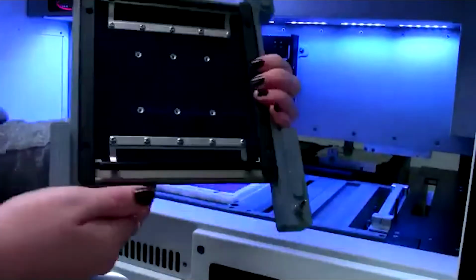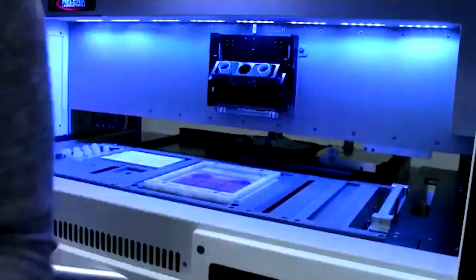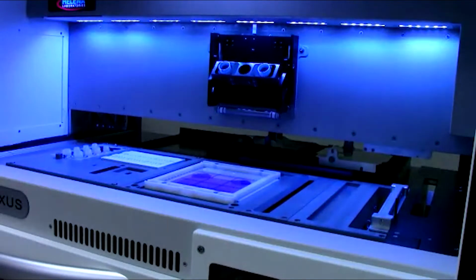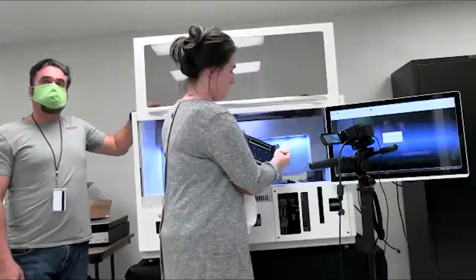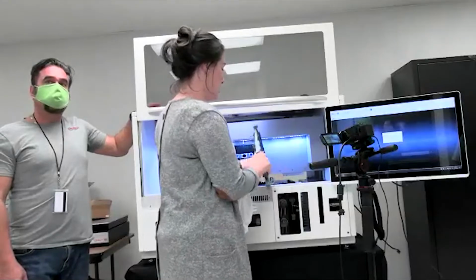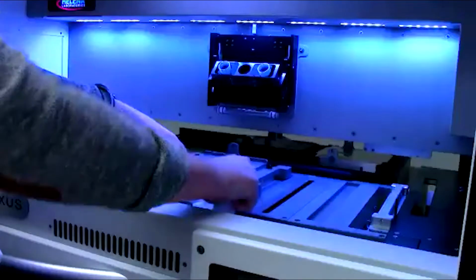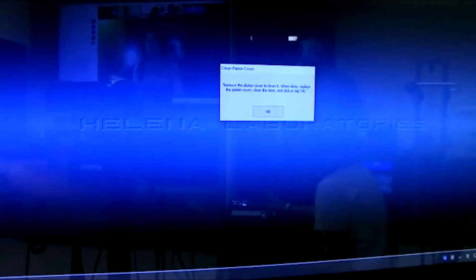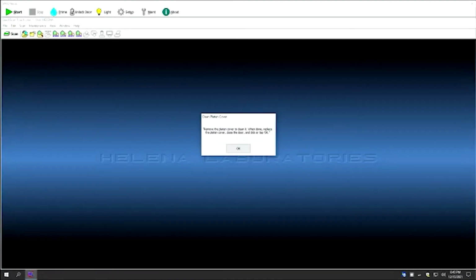And from here, I can wipe down my electrodes to make sure they're not building up soot. And then I'd put it back onto the platen, and you can see the screen is giving me a prompt, and all I have to do is press OK, and it'll move that platen cover back to where it was. And similar processes are in place for flushing the lines of the machine with bleach. Just a quick cleaning procedure, either once a week or once a month.